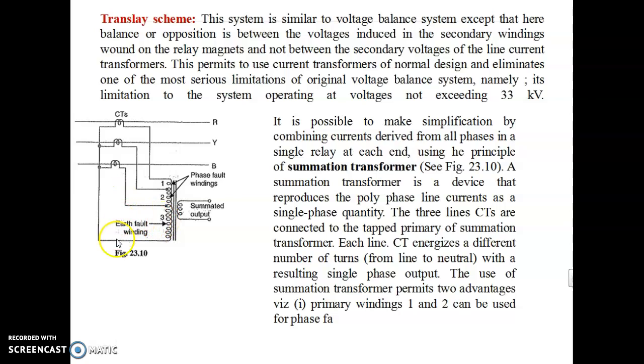Okay, the three line CTs are connected to the tapped primary of the summation transformer here. Each line CT is energized at a different number of turns, with a resulting single output. Okay, see, primary windings 1 and 2 can be used for the phase faults, whereas 3 can be used for the earth fault. The number of pilot wires required is only 2. Okay, here we are using the summation transformer for combining the phases.